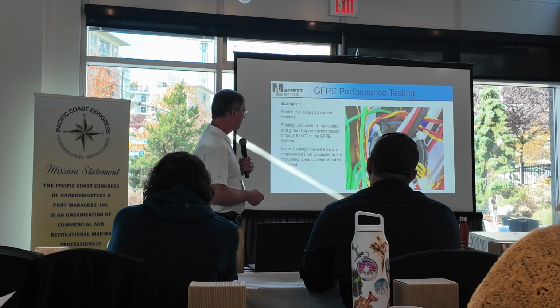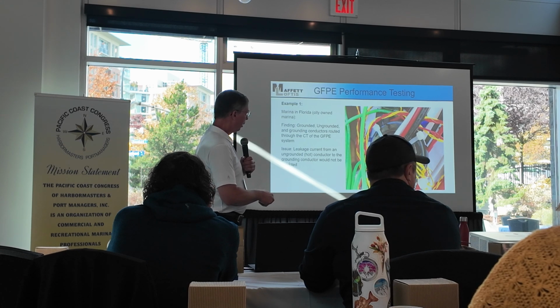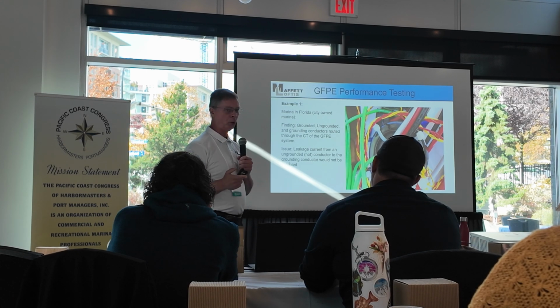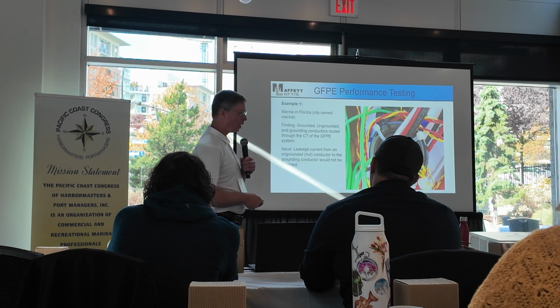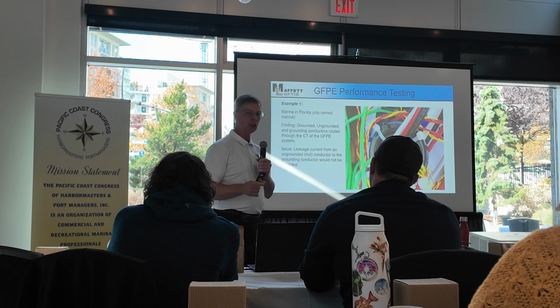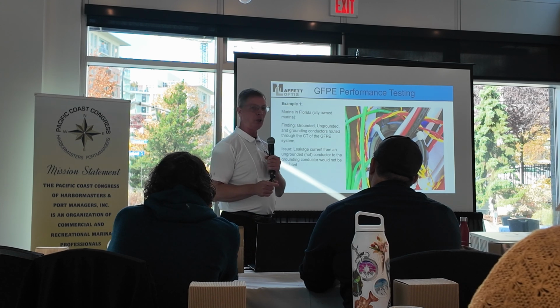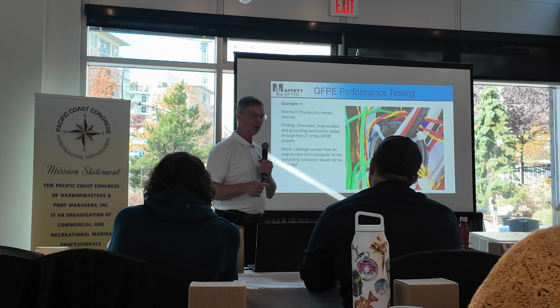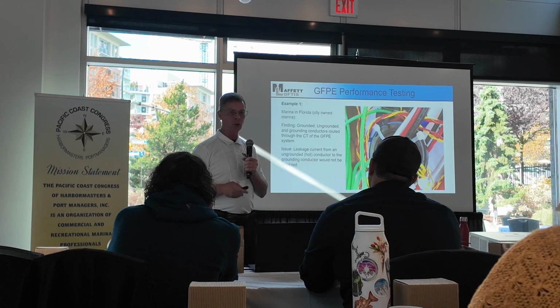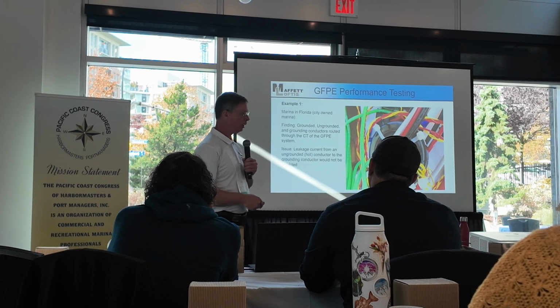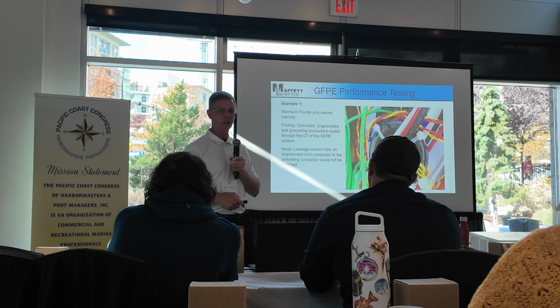Okay, if you look, this is the CT, and in a moment when I go through understanding NEC leakage current, you'll see, and I've got one guy smiling because he probably understands what's happening. The ground wire does not go in there. And no matter how much leakage current I produce on the ground wire, it would not trip. I go up 100 milliamps, 200, 300 milliamps, and it wouldn't trip because that CT never saw it, because that ground wire doesn't belong in that CT.